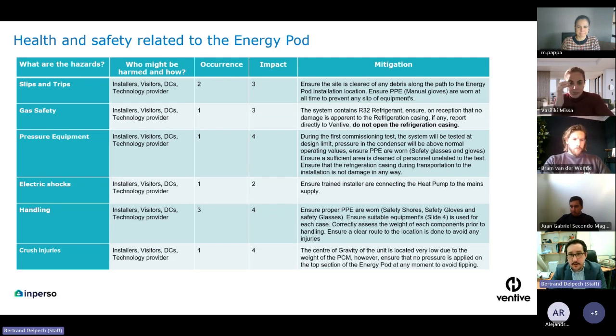Pressurized equipment is similar. Because there is a risk of pressure release, we advise that whenever people are working around or on the heat pump, they wear safety glasses and gloves to protect from projection, and also safety shoes. That's really the main thing. And ensure also that the area around the heat pump is clean, so free of trip hazards or anything like this.